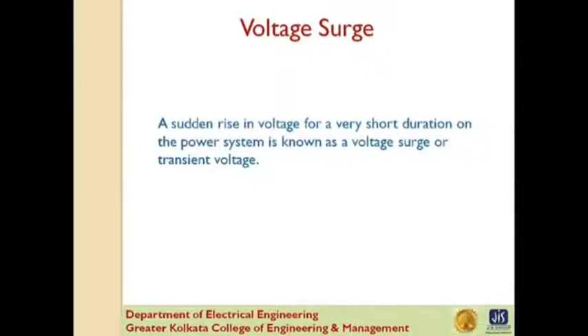By far the most important transients are those caused by lightning striking on a transmission line. When lightning strikes a line, the surge rushes along the line, just as a flood of water rushes along a narrow valley when the retaining wall of a reservoir at its head suddenly gives way. In most cases, such surges may cause the line insulator to flash over and may also damage the nearby transformer, generator, or other equipment connected to the line if not properly protected.